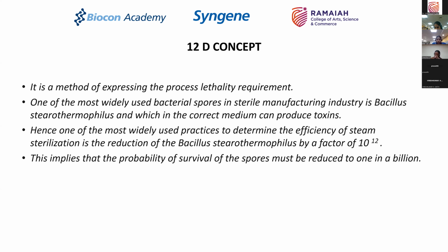Now, what is generally done is that if you want to go to a stage where you want an overkill approach, meaning that you want to kill the microorganisms for sure, and you don't want to take a chance that you go to 10 to the power of 6 but don't know whether in that media you will still see growth, because you are going to keep the product for, say, 2 years. It has a stability of 2 years. So at the end of 2 years, what may happen? I want to go with an overkill approach so nobody survives. Then you use a 12D concept.